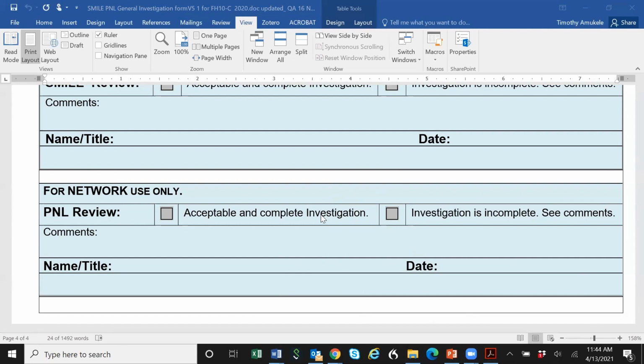Exactly. So I think the way to do it is, when you have a template like this, you can do that kind of investigation. Because what you don't want to do is to say, oh, we failed, but it's probably sample deterioration, without actually doing due diligence. You can see here, we went back and checked our QC. QC was fine. We repeated the results. We checked with our engineer, and he did his function checks and so forth, and they were fine.